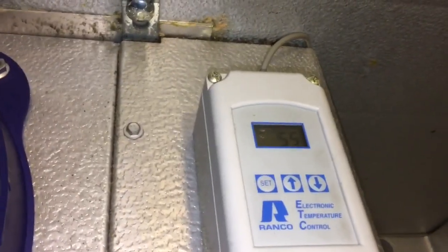Basically cleaning up the fan, the fan guard, the evaporator coil, and then we'll get into the TXV. Doing some pump down on it, things like that. I've got the Field Piece probes hooked up. We're all cleaned up and running. We are at 55 degrees in the box.